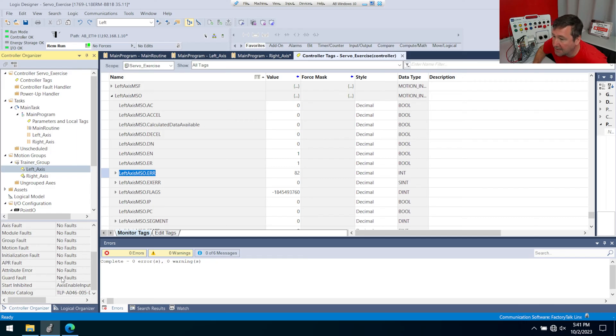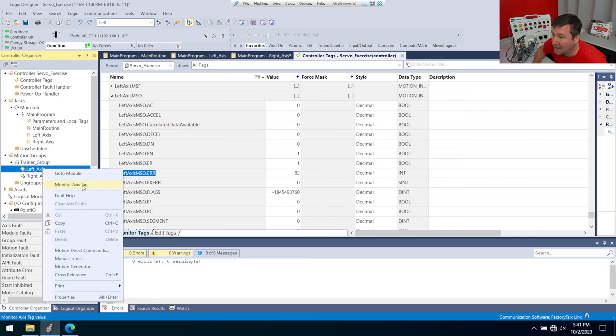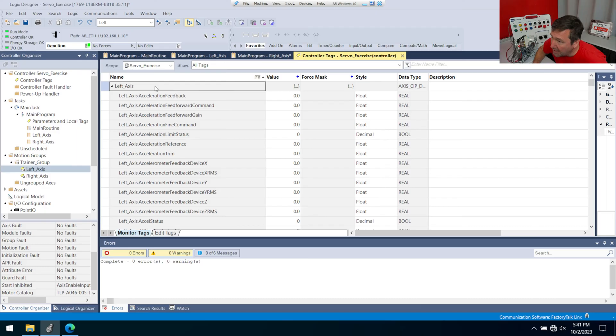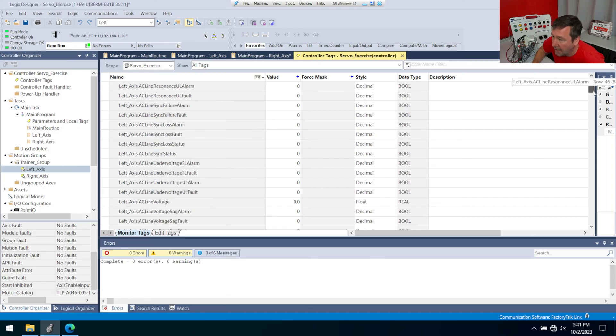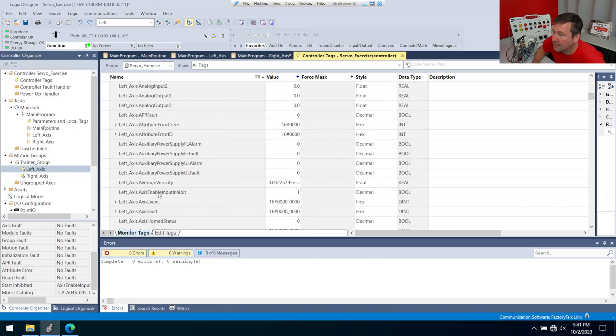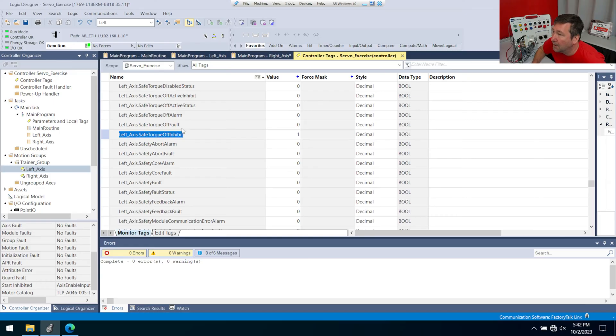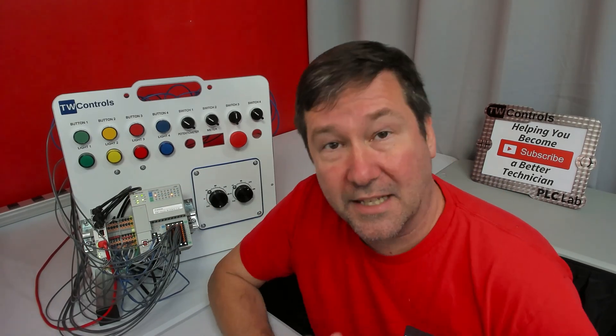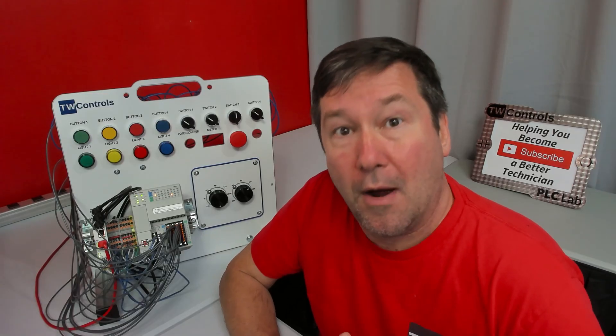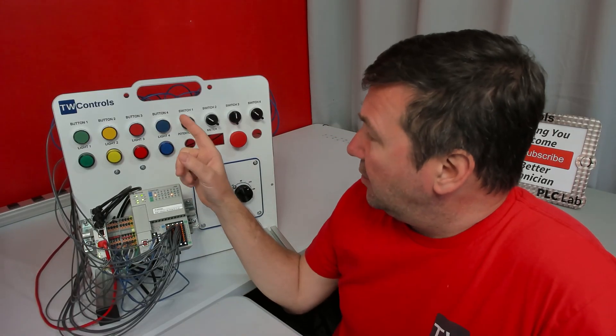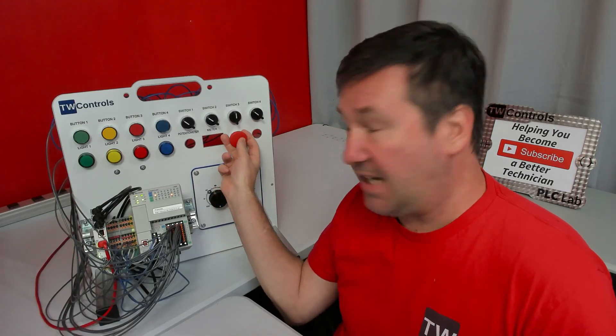We can find both of those tags in our controller tags. The easiest way to get there is to right-click your left axis and select monitor axis tag. That takes us right to it. We're looking for the axis enable input inhibit — go down to axis and there is the axis enable input. The other one is the safe torque off inhibit, and if we go down there's our safe torque off inhibit input. Since those are the two most common ones, let's use those bits to let the operator know why the servo won't turn on.